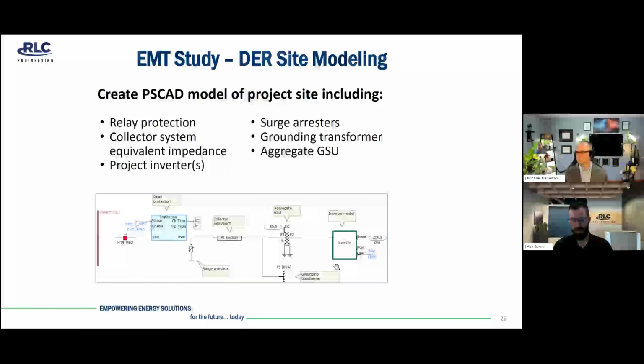Once the inverter model has been validated, the DER site model must then be created within our model. So the following parameters would typically be included. First up would be relay protection, collector system equivalent impedance. If you can see my mouse, I'm kind of circling where those are at in the model here. Project inverters, and these are often aggregated if they're all the same inverter, but sometimes if a site has multiple types of inverters or they're operating at different ratings, we'll model them explicitly to ensure that accuracy is captured.